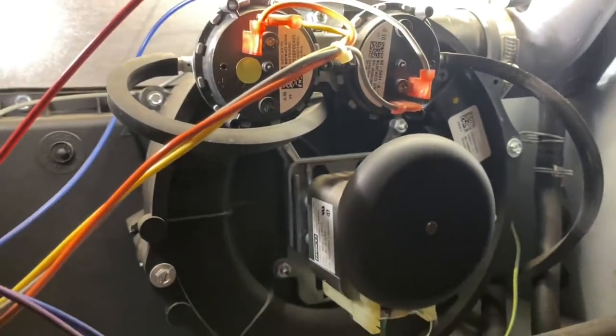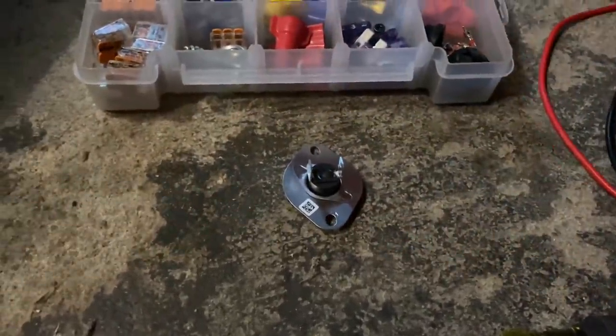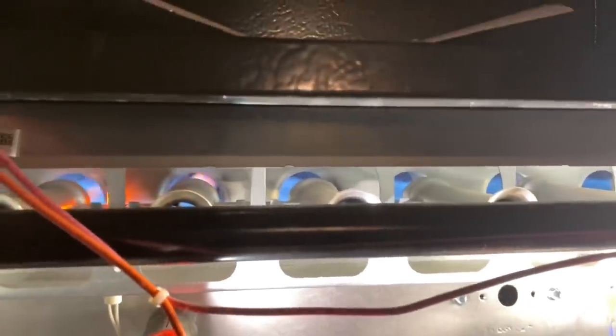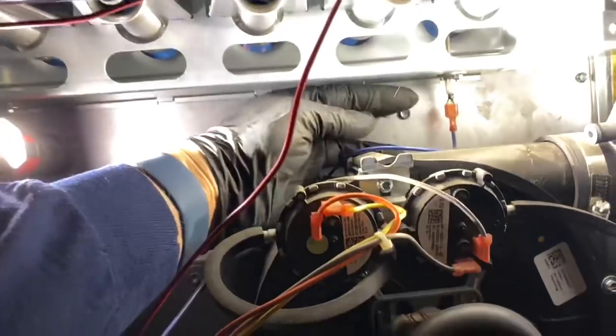We have the inducer motor calling. Shortly thereafter the hot surface igniter is going to come on and we should ohm out that sensor. The sensor reads open — and we do have ignition. So we have a bad flame sensor.